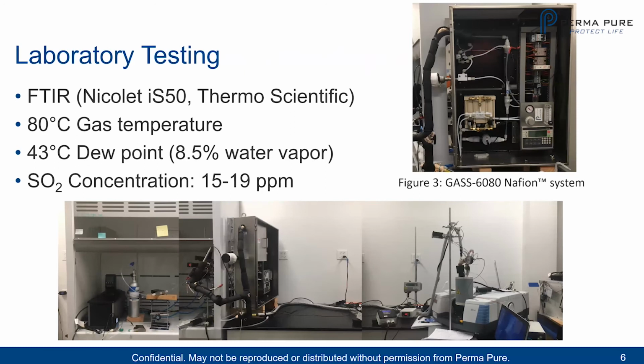So let's look at what we've done in our laboratory. In our laboratory, we used a Nicolet iS50 Thermo Scientific FTIR. We used an 80 degrees C gas temperature with a 43 degrees C dew point, or 8.5% water vapor. And we're looking at an SO2 concentration of 15 to 19 ppm. So we used our GASS-6080 Nafion system that's shown on the top right there. That's one of our systems we build. And below is our test setup where we are generating the sample gas and putting that into the sample conditioning system to remove the water, and then we're analyzing that with the FTIR. We try to emulate a typical sample gas that we see at some of our customers.